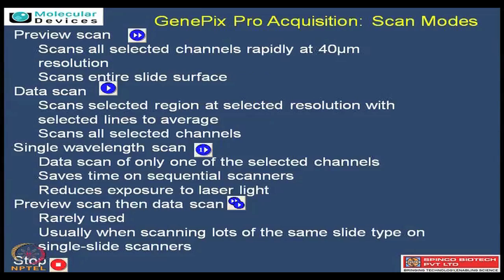The basic GUI contains three different areas. The first one is image and laser controls, where you select which kind of laser you are going to use. The second one is different features used for controlling the image. Towards the right-hand side there is a pane for hardware controls. The basic hardware control is the auto PMT and other adjustments, for which we use the preview scan. There are different tabs which allow you to go for the data scan and the preview scan based on the laser and application you are using.